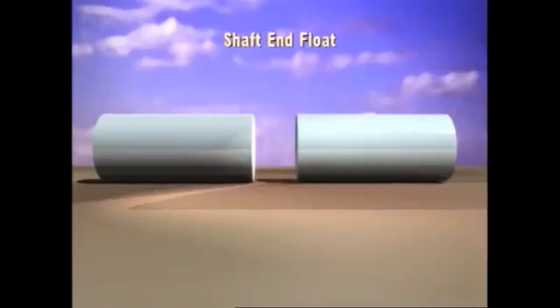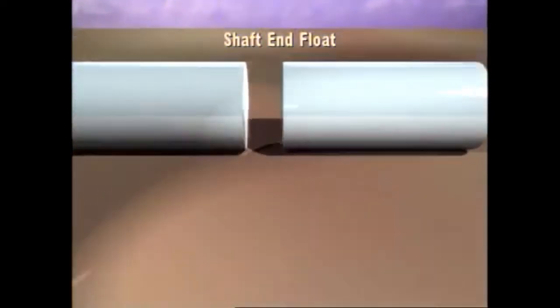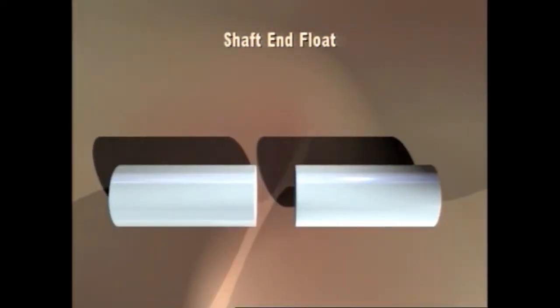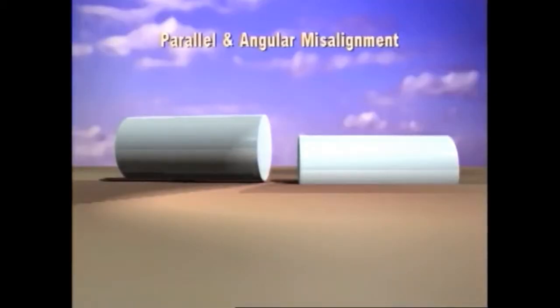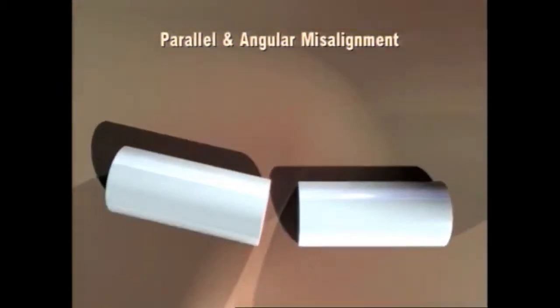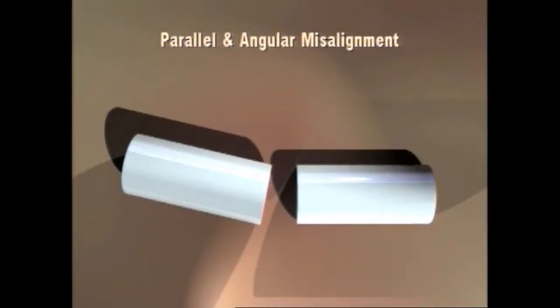angular misalignment. In addition to misalignment, we're also concerned with end float, which is an in and out movement of the shaft along the axis of the shaft. In reality, misalignment usually includes both parallel and angular misalignment. The goal when aligning machines is to reduce the angular and parallel misalignment to a minimum. Misalignment is one of the primary causes of excessive vibration in pump stations, motors, and pumps. This misalignment causes early bearing, mechanical seal, and packing failure.